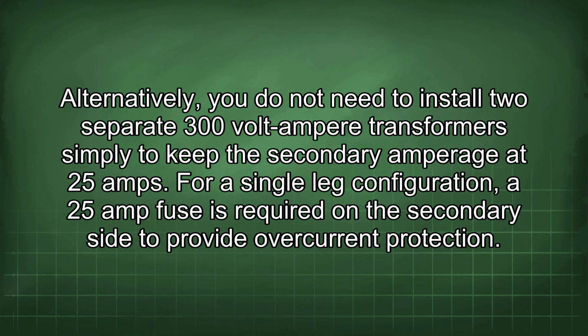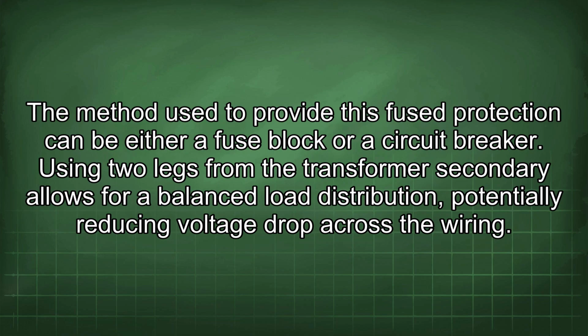Alternatively, you do not need to install 2 separate 300-volt ampere transformers simply to keep the secondary amperage at 25 amps. For a single leg configuration, a 25 amp fuse is required on the secondary side to provide overcurrent protection. The method used to provide this fuse protection can be either a fuse block or a circuit breaker.